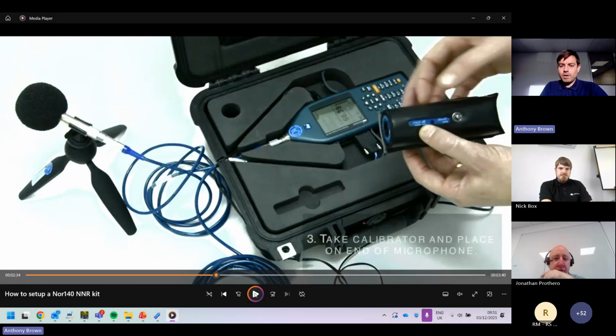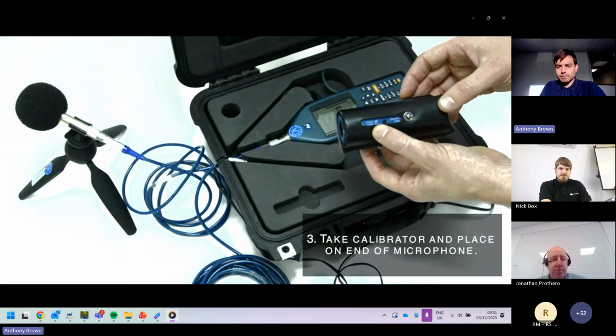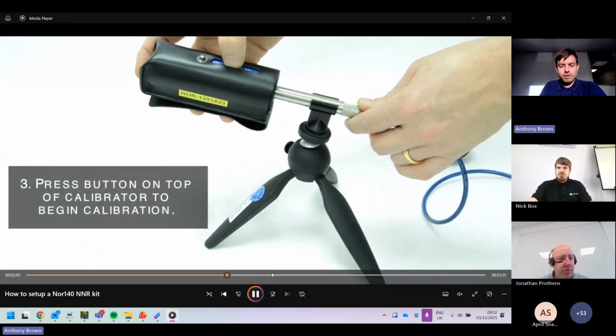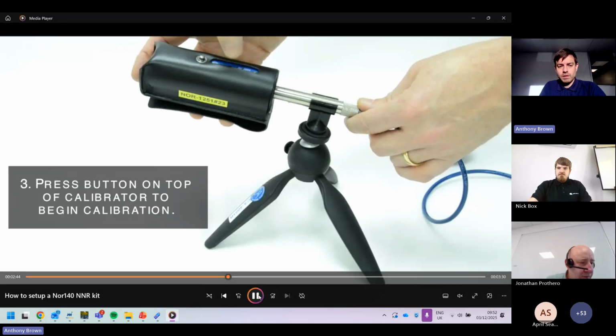For the calibration, you're going to need this calibrator. On the right-hand side we've got a calibrator - you'll have one that's either round in the box with a number on it that says 114 dB, or you might have a rectangle version. We'd like you to take out that calibrator if you have one; if you don't, do not panic. Just place it on the end of your microphone - take the windshield off the microphone and place the calibrator on the end, then turn this on.